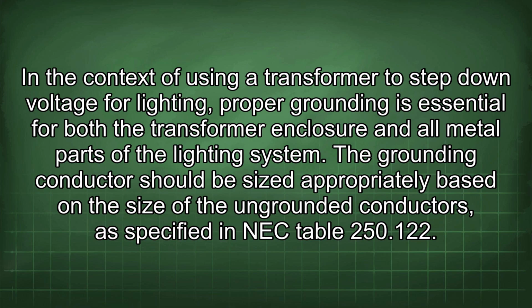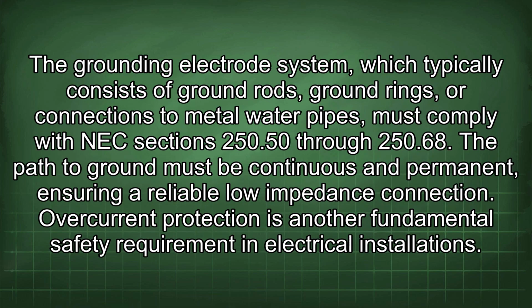The grounding conductors should be sized appropriately based on the size of the ungrounded conductors, as specified in NEC Table 250.122. The grounding electrode system, which typically consists of ground rods, ground rings, or connections to metal water pipes, must comply with NEC sections 250.50 through 250.68. The path to ground must be continuous and permanent, ensuring a reliable low impedance connection.